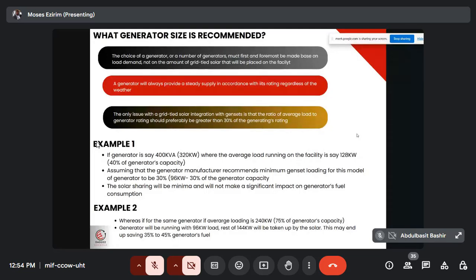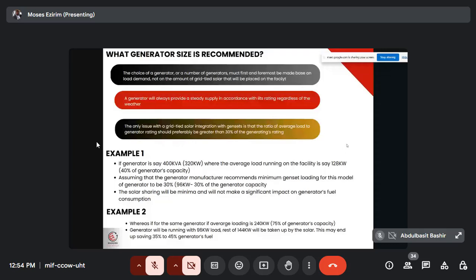For example, let's assume a new facility wants to come on board. You don't size that generator based on PV or the solar capacity. No, they will size their generator based on their load. So let's assume that they've done their own sizing. The generator should be able to withstand the peak load.